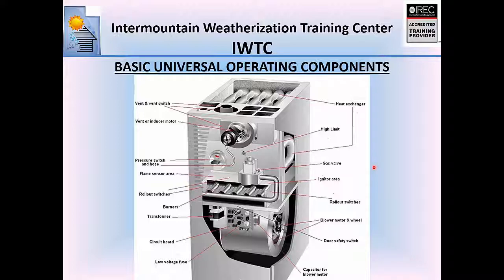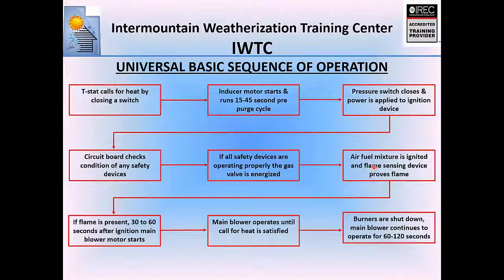All right. This is what we call the universal basic sequence of operation. Every modern furnace you run across will have this basic sequence of operation. Your T-stat's going to call for heat by simply closing a switch. That's all a thermostat is, a glorified light switch. It's either open or closed, and when it's closed, it's calling for something.